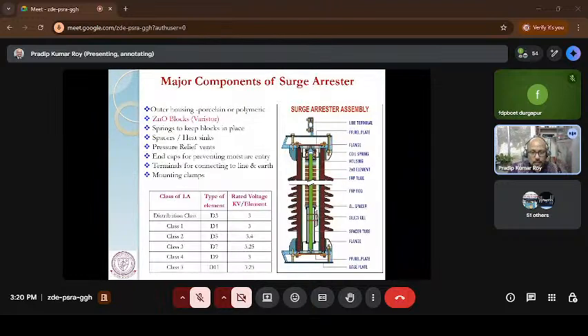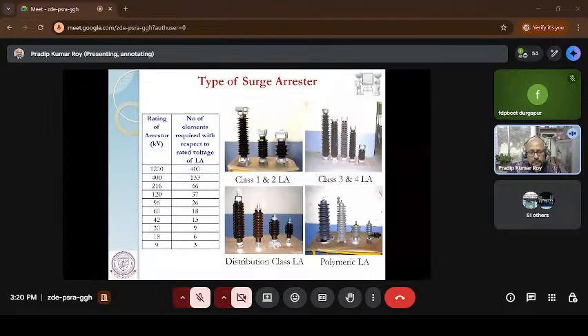Now, if you look at the materials classifications, there are different kinds of blocks. If you look back at the previous slide, there are different classes, and in different classes there are different kinds of blocks, and the different blocks have different ratings. For example, the D3 block has rating 3, D4 block rating 3, D5 block 3.4. So they have different ratings. For example, if I look at this figure, I want a 400 kV surge arrestor where the rating is 3. If the rating is 3, that means I need 133 blocks to make a 400 kV surge arrestor.